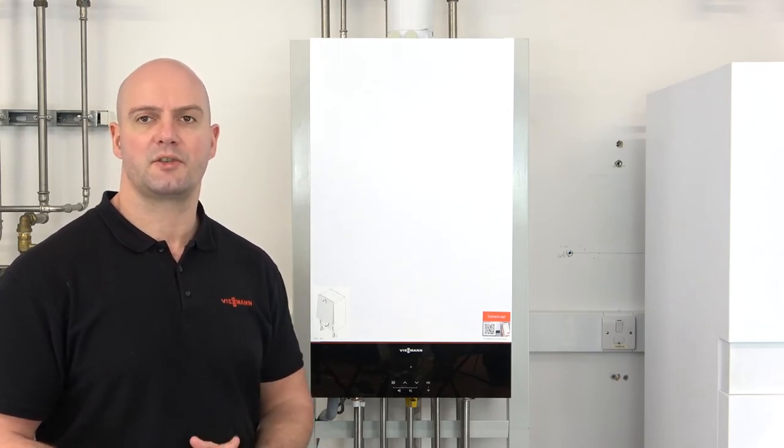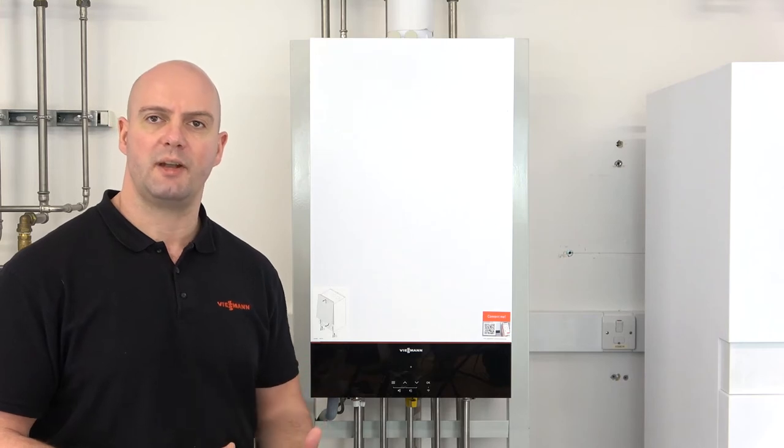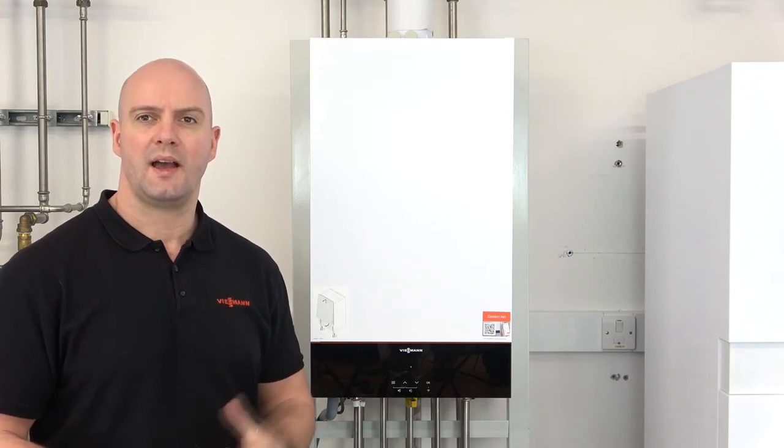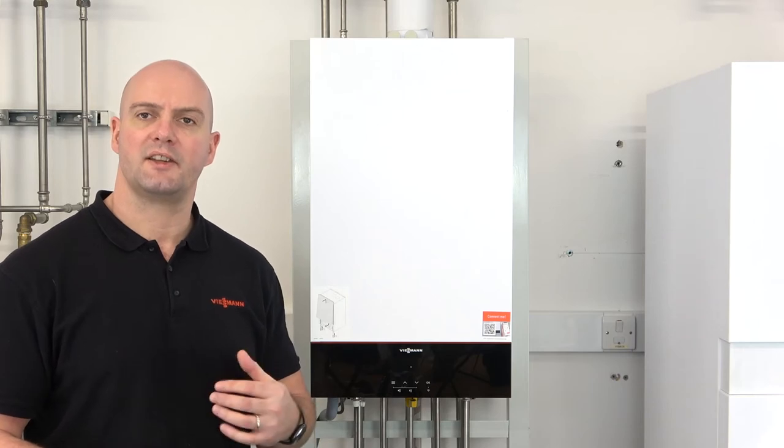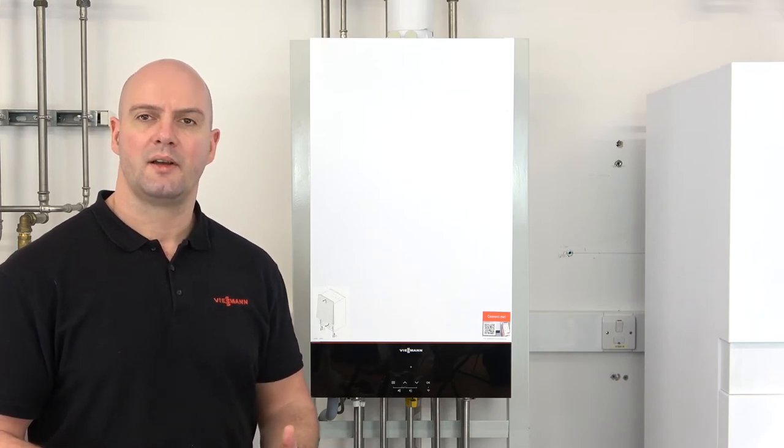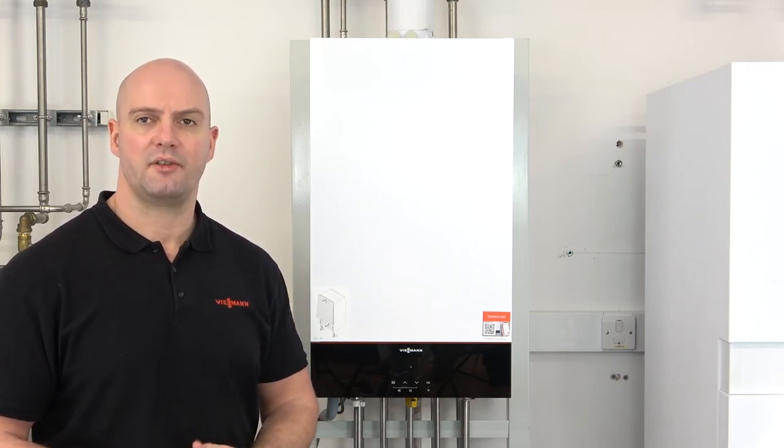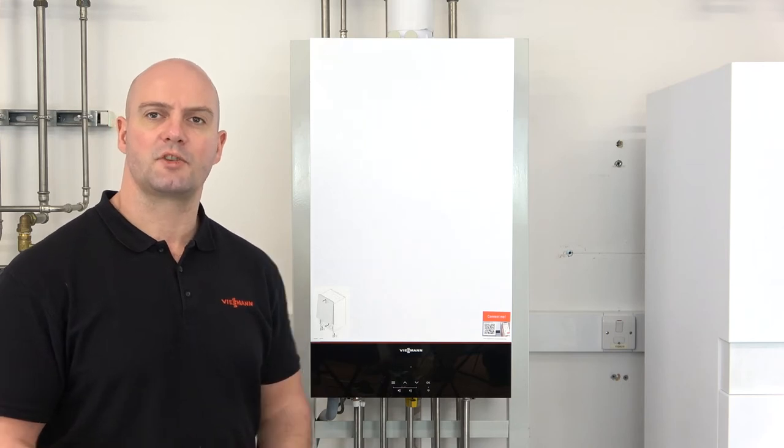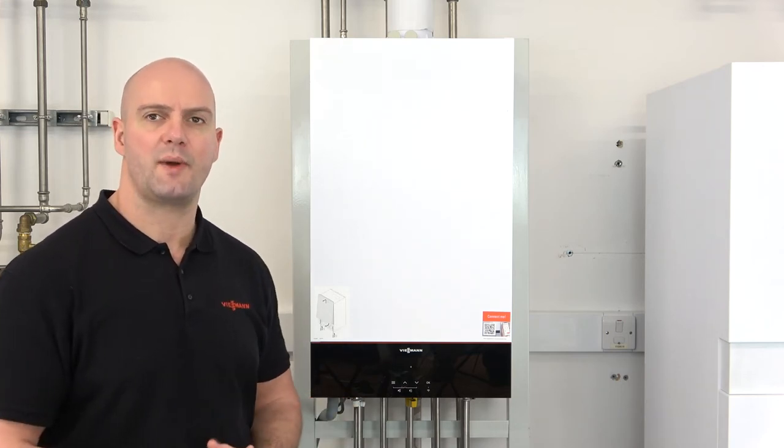In the service menu we can do such things as put the boiler into its minimum and maximum rate, accessing the commissioning mode, accessing the parameter menu, and also looking at the previous error history for the boiler. So we're just going to have a look at the front panel now and I'll show you how to access the B codes.